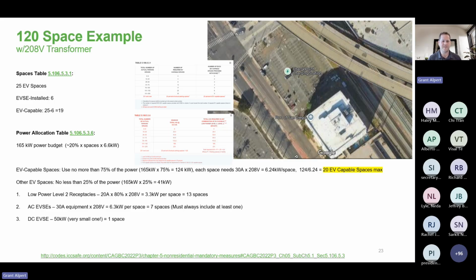So the other spaces need to be EV charging stations. Based on the fact that each space requires 30 amps and you have a 208 volt transformer, there needs to be 6.24 kilowatts per space. And that 124 kilowatts divided by 6.24 results in a total of 20 EV capable spaces. So in the space method, there are 19 EV capable required, or a minimum of 19 EV capable. With power allocation, you can have a max of 20 EV capable spaces installed. So one more, not a huge difference.